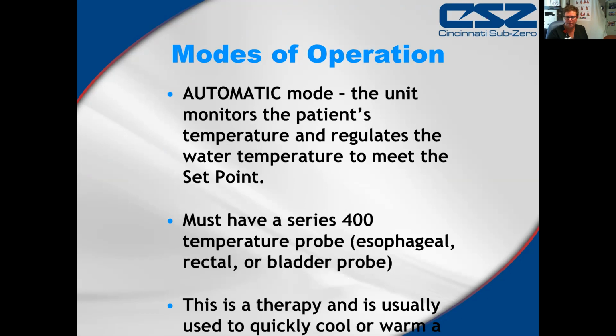So our target temperature at the New Brunswick Heart Center for cooling post-cardiac arrest is between 32 and 34 degrees. So what we do is we set the temperature for the patient to be at 34. And when we do that, the machine will kick in and cool that patient, but it knows what the patient's own temperature is because we have it plugged into the side, and it can sense this feedback, and it can increase or decrease the temperature of the water.